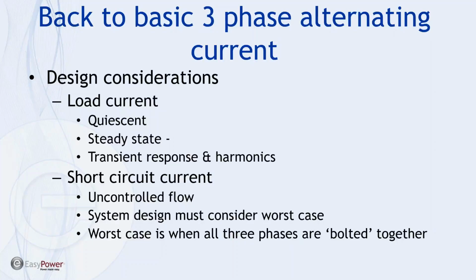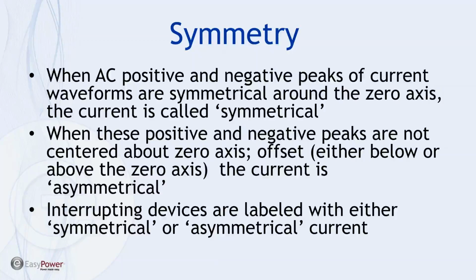So in terms of short circuit current, symmetry is defined as the point when all the AC positive and negative peaks are symmetrical around the zero axis. And again, this is what we will get in a three-phase bolted fault. On the other hand, when these positive and negative peaks are offset or centered somewhere above or below the zero axis, then this current is considered asymmetrical.